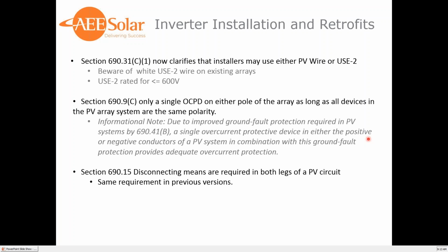Section 690.9, only a single overcurrent protection device on either pole of the array, as long as all devices in the PV system are the same polarity. So essentially, overcurrent protection is only required on one pole as long as it's the same polarity on the system. So as long as it's all negatives, you're fine, or all positives, you're fine. In section 690.15, disconnecting means are required in both legs of the PV circuit. This is the same requirement as in previous versions, so not a huge change there.